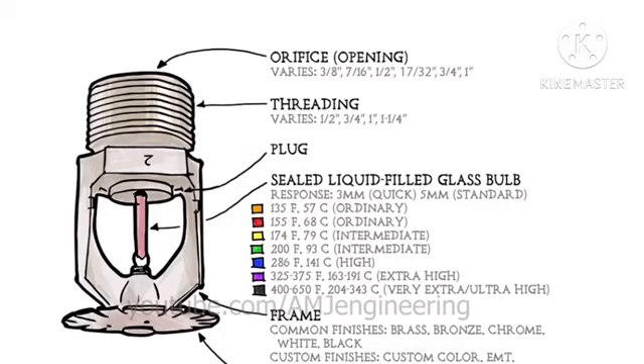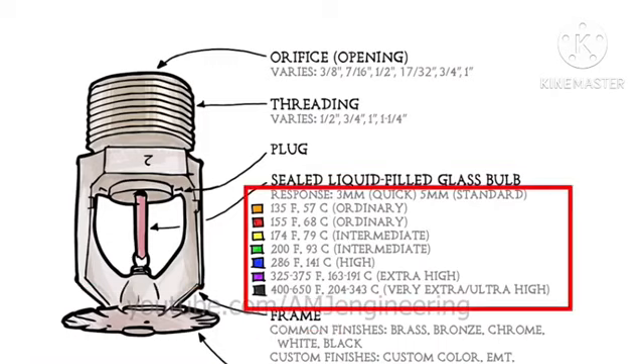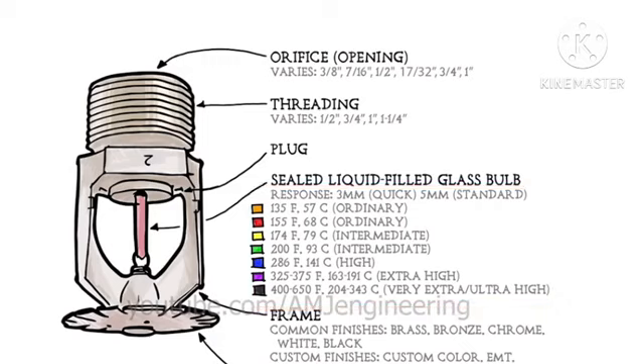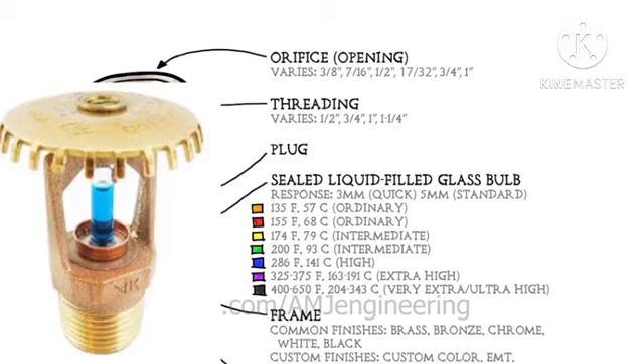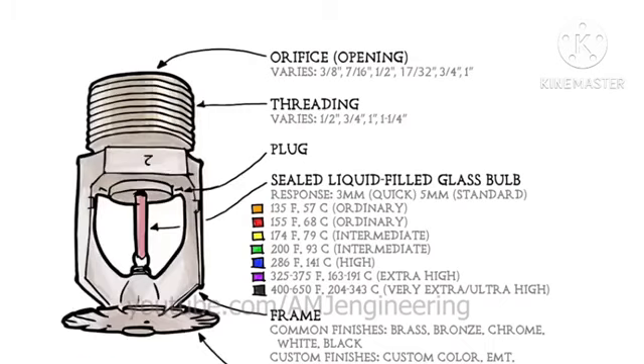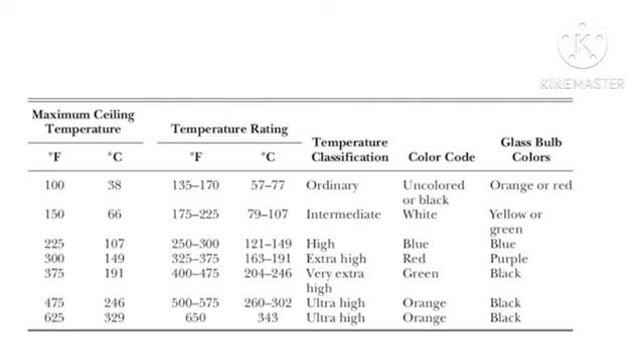Nearly all fire sprinklers are composed of the same components: a sealing assembly or plug that prevents water from escaping, a heat-sensitive element that allows water to flow at a given temperature, a deflector that distributes water effectively, and a frame. The sprinkler's temperature rating is the temperature at which the sprinkler will activate. Options range from 135 to 650 degrees Fahrenheit. These ratings can be identified by the color of the liquid inside the bulb in the case of glass bulb sprinklers. The selection is taken from NFPA 13 Table 7.2.4.1 based on the hazard class for the structure that the fire sprinkler system is protecting.